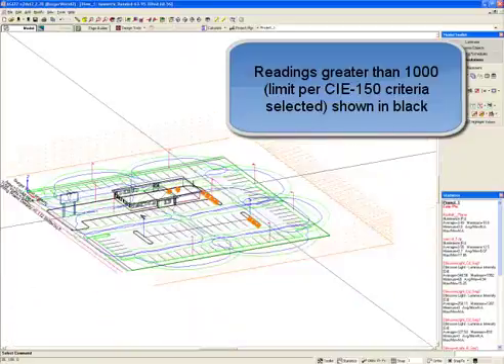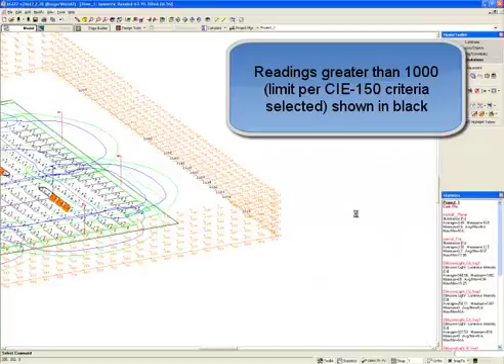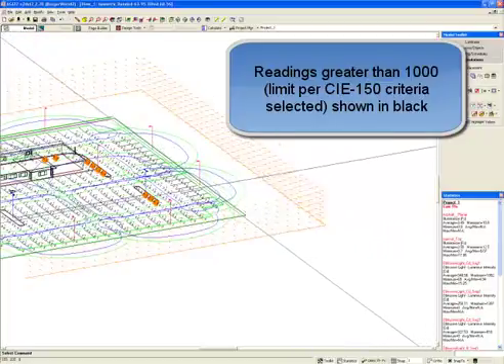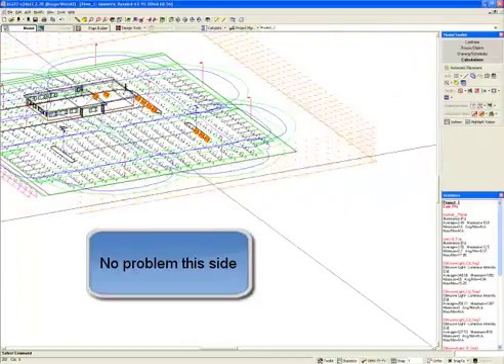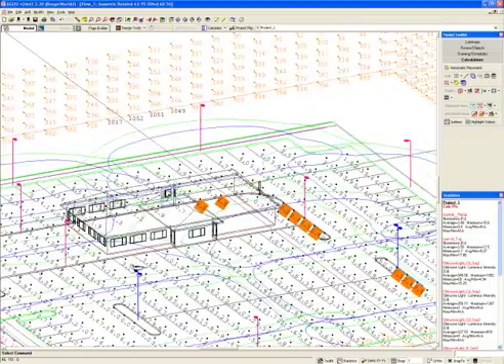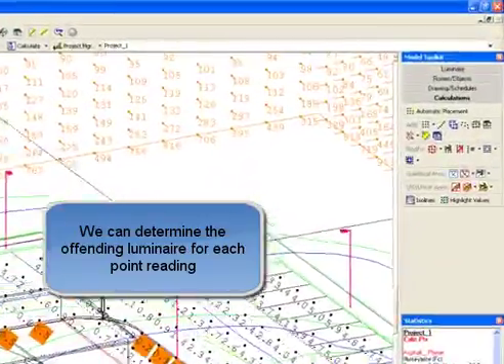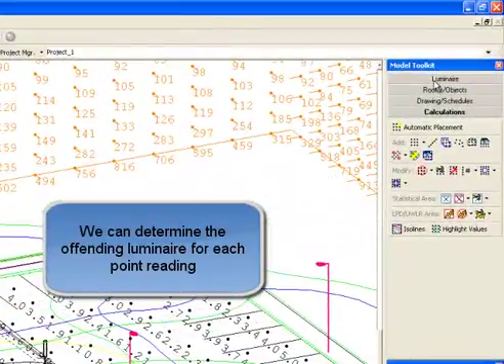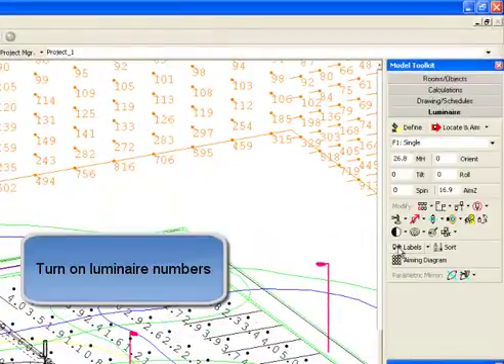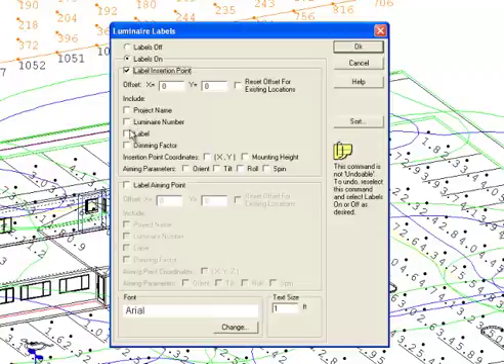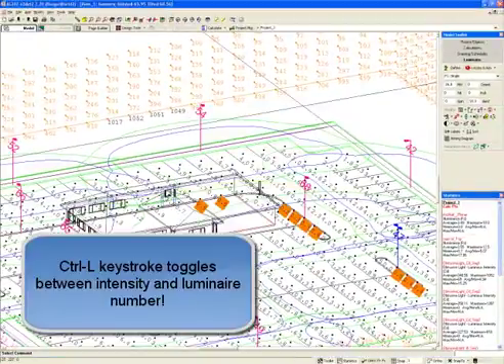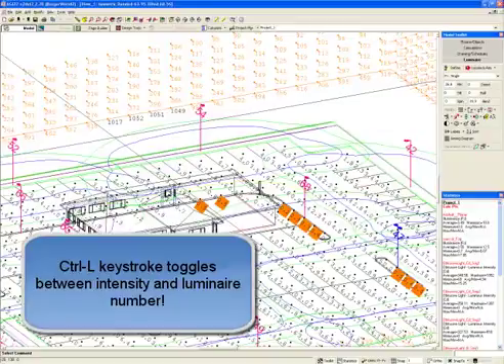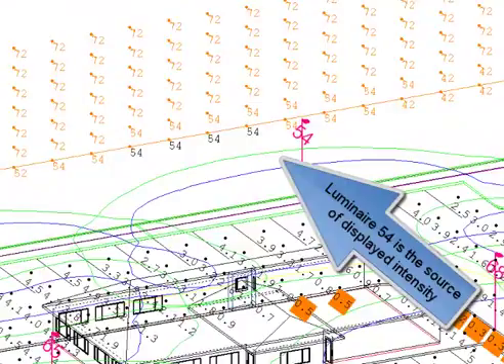The maximum luminous intensity in candela from any single luminaire is displayed. Readings greater than 1000, limit per CIE 150 criteria, are shown in black. No problem with this side. We can determine the offending luminaire for each point reading. To turn on luminaire numbers, we go to the labels command and make sure the luminaire number appears for each luminaire.